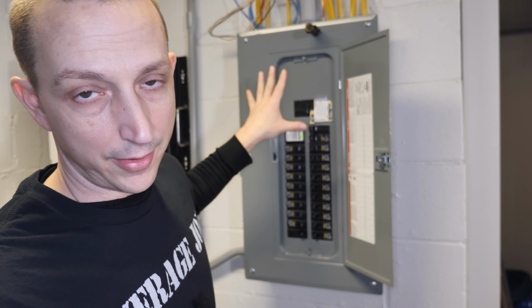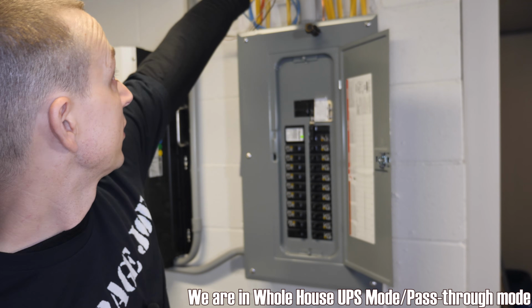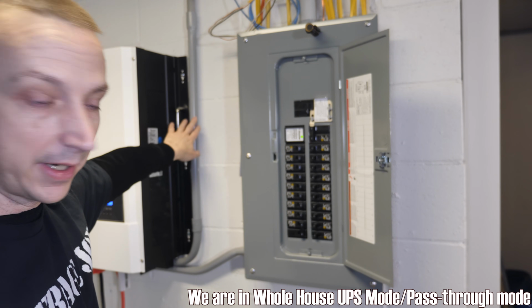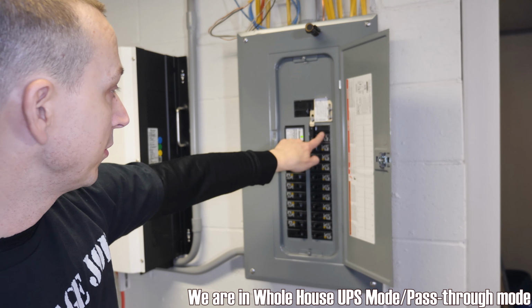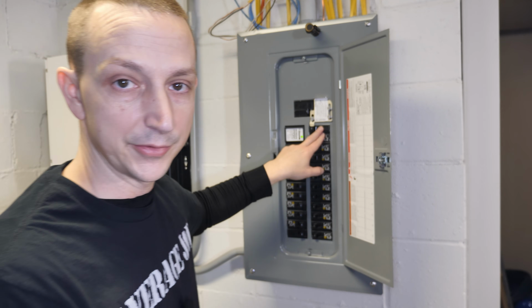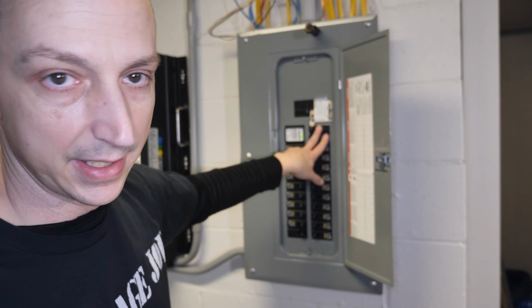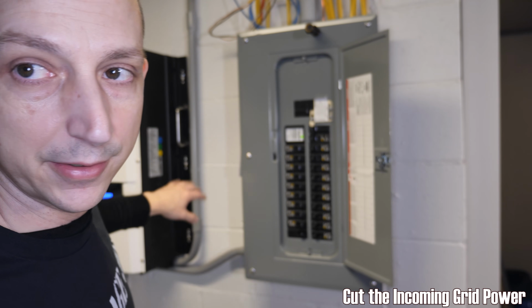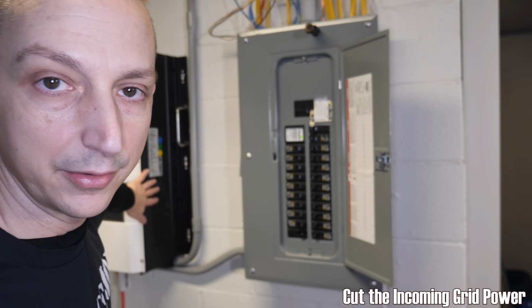Alrighty, so now we are not off grid quite yet because we're still coming in through these wires right here, coming out right here, and supplying this right here. What I have to do to go off grid for this test is turn off those two circuit breakers on the bottom of the inverter. So we'll go ahead and do that real quick.